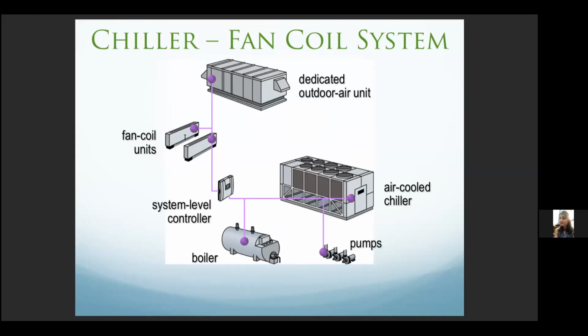corridors on every floor. And the system level controller, there are going to be sensors on the floor. The system level controller is going to know when those sensors can change the temperature. It can change the supply air temperature reading of the outdoor air unit based on those temperature readings. If we need an increased temperature inside the fan coil, the space is not being satisfied, it'll tell the chiller to kick on or run harder and make sure cool enough water is being supplied to the fan coil units to satisfy space temperature. Or in heating season, it'll tell the boiler to do so, and the pumps are going to work in conjunction with the air-cooled chiller or the boilers, depending on the system, and they are also going to be controlled by the system level controller.